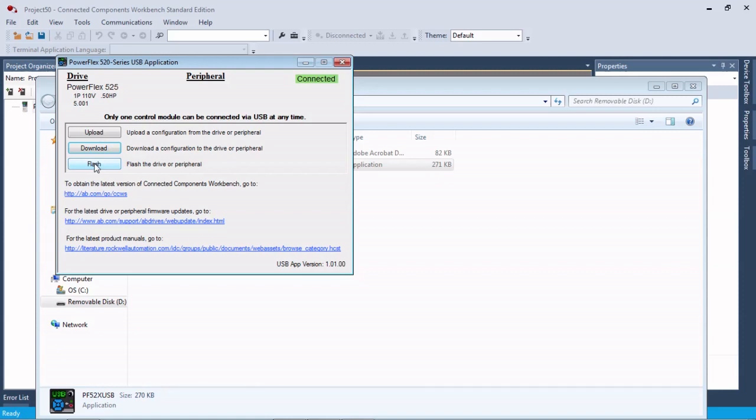One thing to remember is if you use this for a flash, the drive is not flashed until it's powered up under full power. So if you use this tool to flash the control unit, you need to power up under full power before you can change parameters after a flash. Otherwise you're just going to write over your parameter settings.